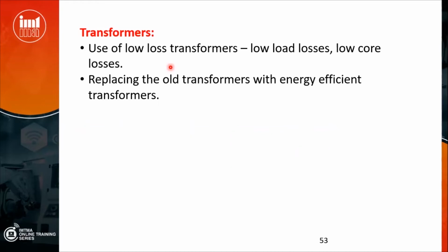Even if you don't load the transformer, there will be core losses taking place. So if the core materials are not of good quality, there will be a continuous loss in the transformer, adding to the energy loss. So you must be careful and ask for the details when replacing the old transformer with an energy efficient transformer. Similar to motors, you must have a plan. Whenever you think of this, please keep that in mind.